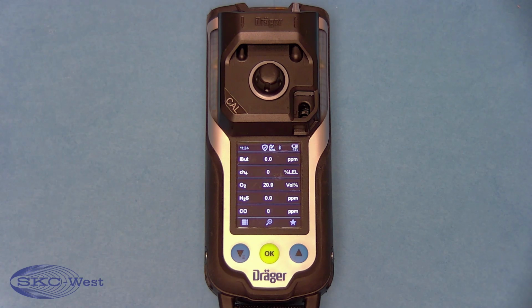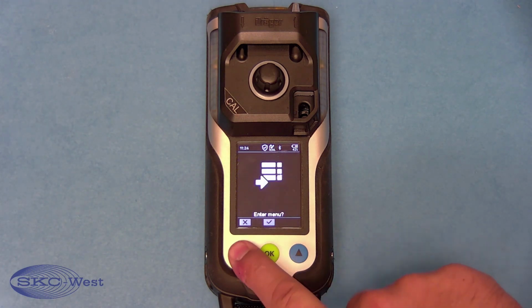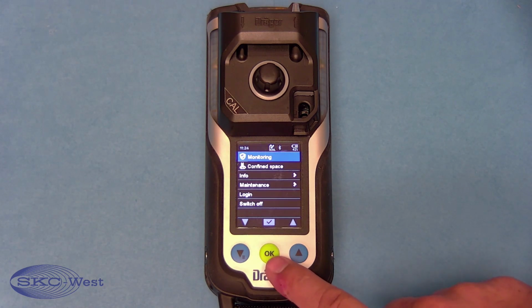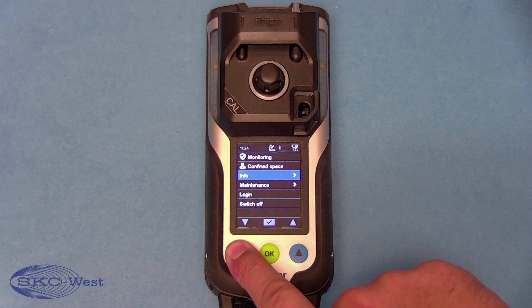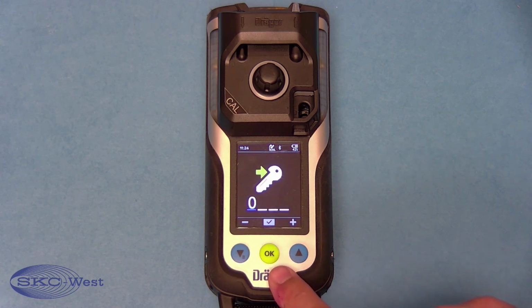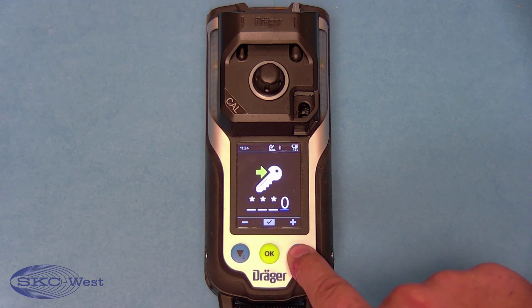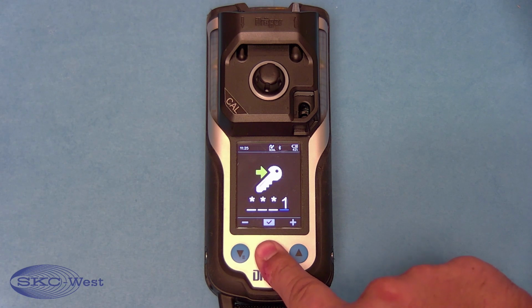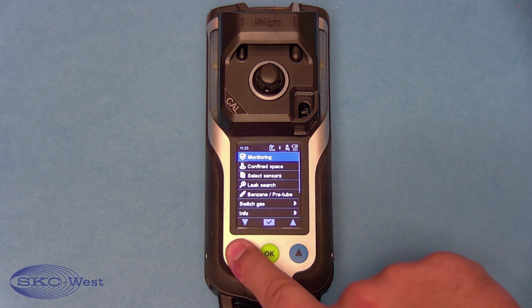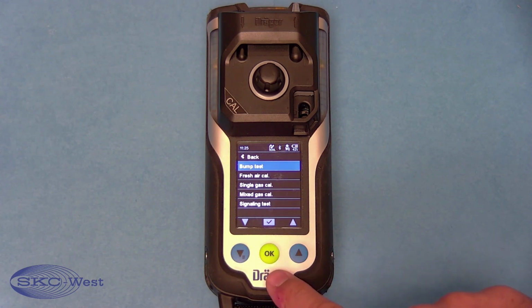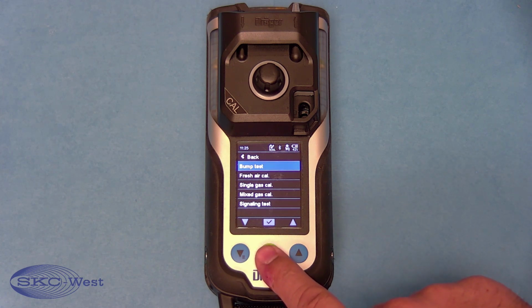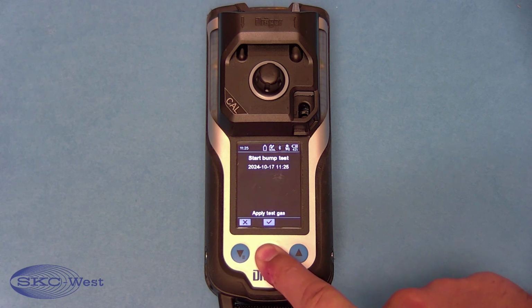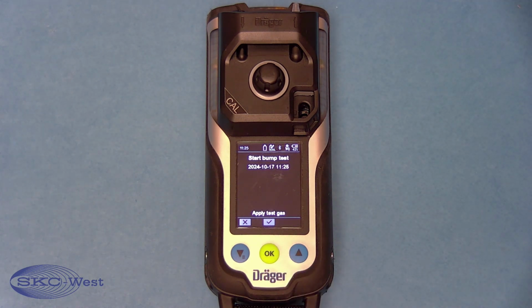Now on the instrument, we're going to go into the menu, the left arrow button, and we're going to hit OK. We're going to arrow down to the login screen, and we're going to hit OK. And the password here is 0001. So on the last 0, you're going to push the up arrow to get to 1 and hit OK. We're going to arrow down to maintenance. Hit OK. Bump test should be highlighted, and we're going to be bump testing the standard 4-gas configuration. Press OK, and now we apply gas.